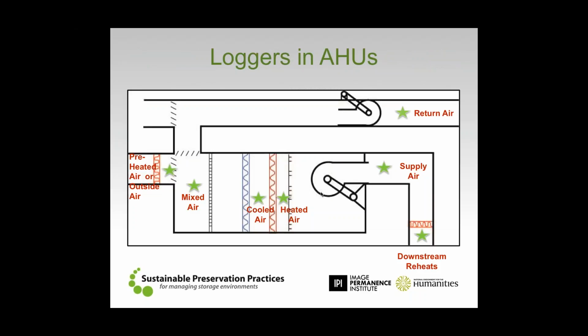This diagram just shows a couple of examples of very typical places where we might find data loggers within the airstream. Oftentimes we're looking, first and foremost, for the return air condition that comes back from the space to understand what the collection may have felt, or a blend of that. But we're also looking to see the condition of the air that's being sent into the space. And that might be a logger that we call the supply air over in this location, or even further downstream if we have some sort of terminal equipment, as we discussed last month, in that ductwork before it actually goes into the space. And then in the interim, we're looking again to find out what type of work we've done to that air as it's moved through the loop.